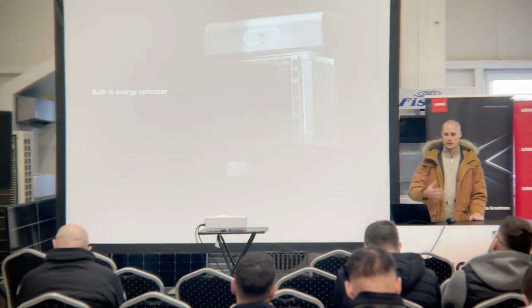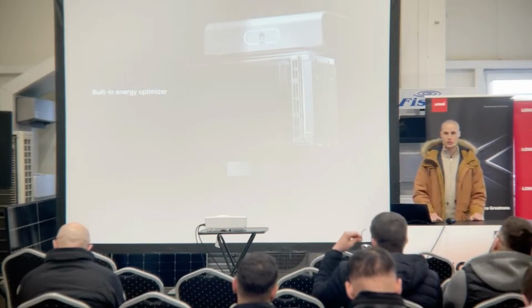Just like the previous versions, it has a built-in energy optimizer in each pack, which allows you to charge and discharge each pack at maximum capacity. So if you install a tower with 2 battery packs and later expand it, say 3 years later, the capacity will be different on those older packs. If you install a new one with 100% state of health and the rest are at 95%, there's a 5% difference between the two. Without the optimizer, you could only use 95% of the newly installed module, but with the optimizer, you can use 100% of each battery pack. That's a great advantage, and I think Huawei is the only brand that has this optimizer inside the battery cells, so it's a really useful feature.